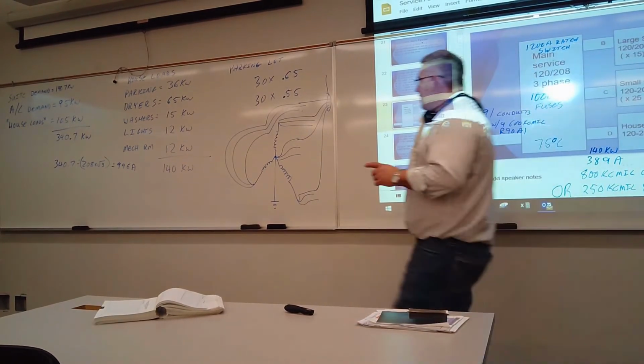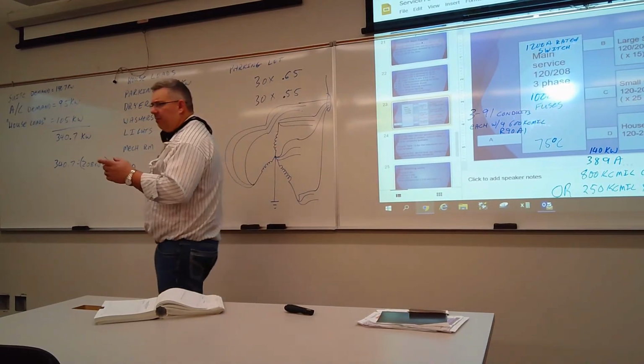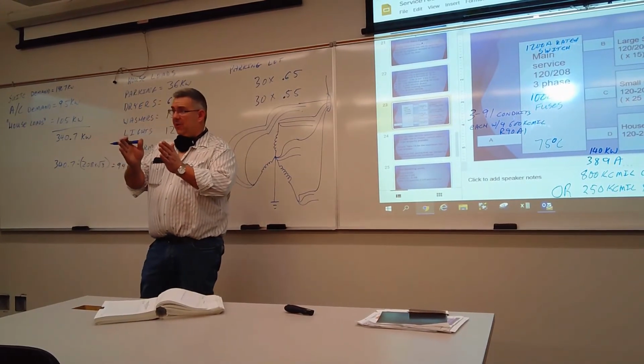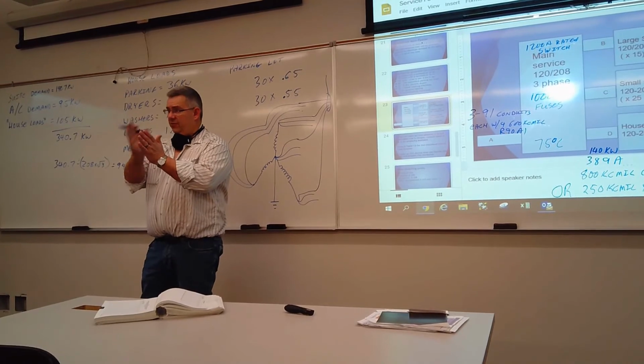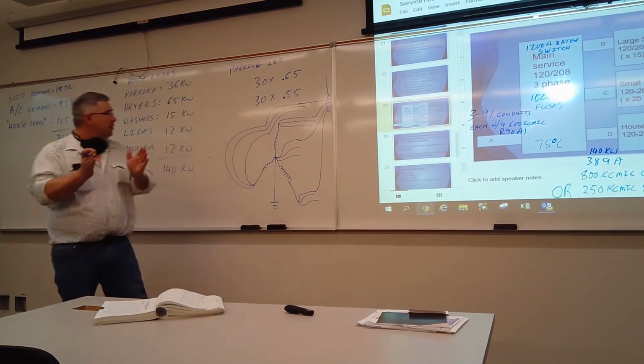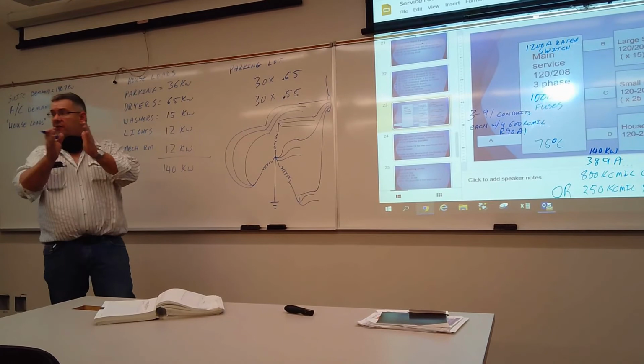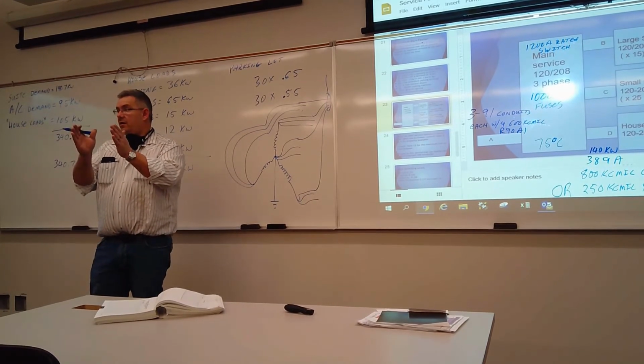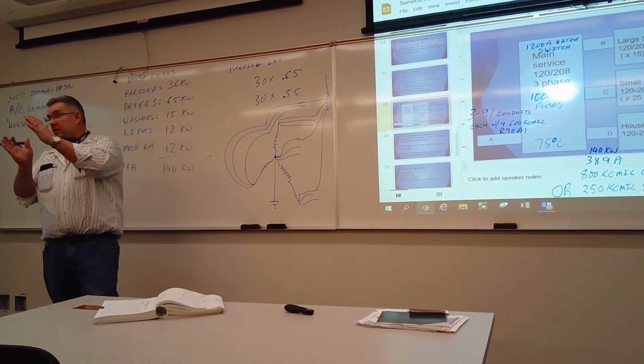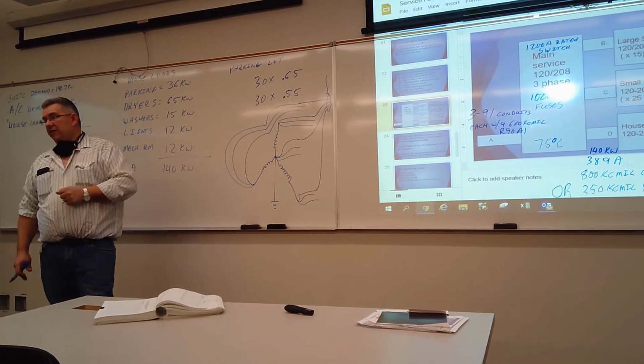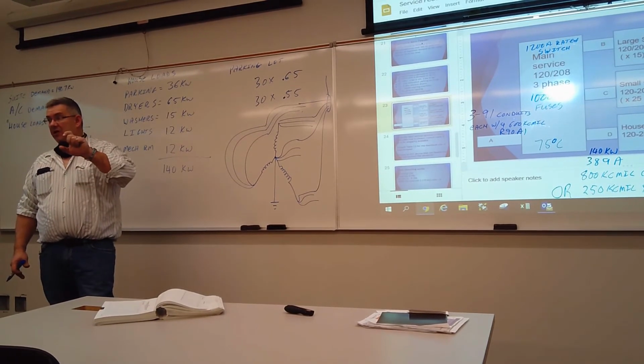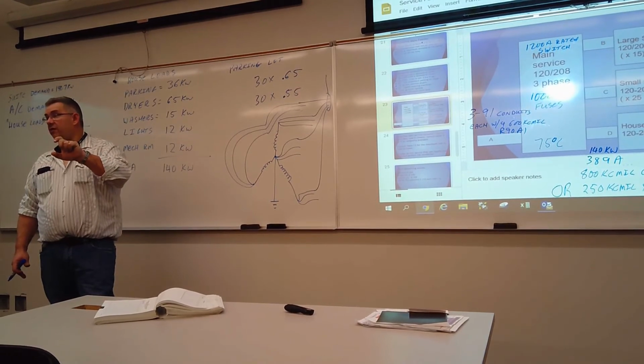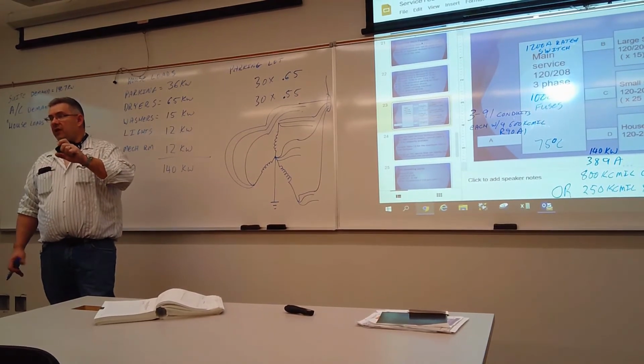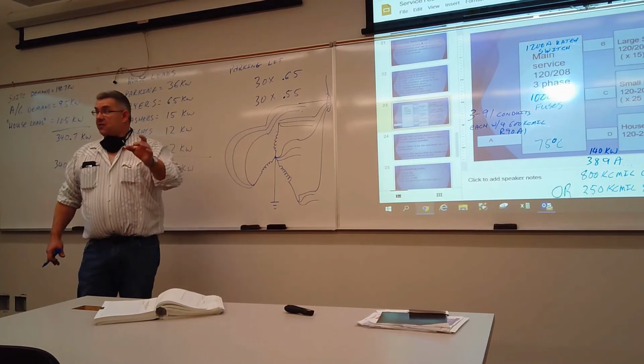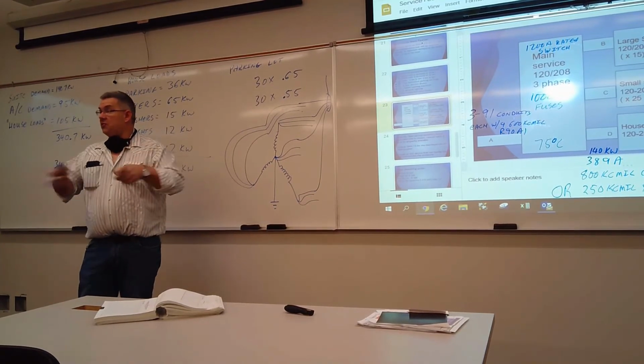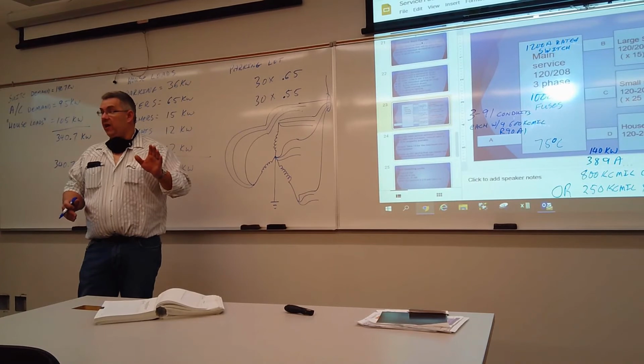There's a couple different ways it can be done. You could just have a bus bar that you mount, with three lugs, good for whatever, for 600 or bigger on a common bus, and then you run out and you do the same thing at the other end. Sometimes you'll have lugs that are rated to put multiple conductors under. They have to be rated for it. You can't just take a lug that's good for 750 and say, oh, well, two 250s will fit in there and tighten her down. That's not okay.